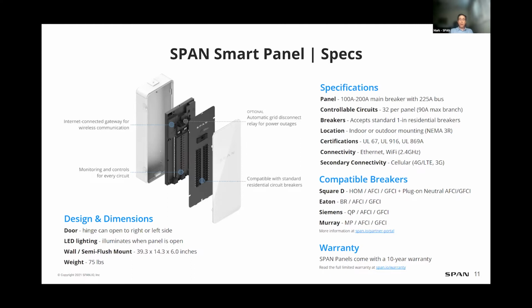We accept standard 1-inch breakers from different manufacturers. We've done testing and we're compatible — there's a section on the slide about Square D, Eaton, Siemens, and Murray. What this does for you is give a lot of choice. There have been all kinds of supply challenges over the last year, and there may be pricing differentials. So the ability to choose the breakers and install what you need on a given job can really help your business have flexibility, especially in these tight times on breaker supply.